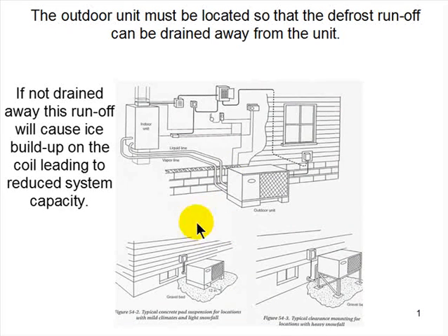But in other climates, you know, you may have to get this thing up on a stand. You've got to be above not the snowfall line, but the drift line for the position this thing is in. And it's always a good idea to have a gravel pit here. You know, dig down about a foot or so, fill that area with gravel, bring it up level, and then set your frame or whatever you're doing on top of that. So any water runoff drains right away.